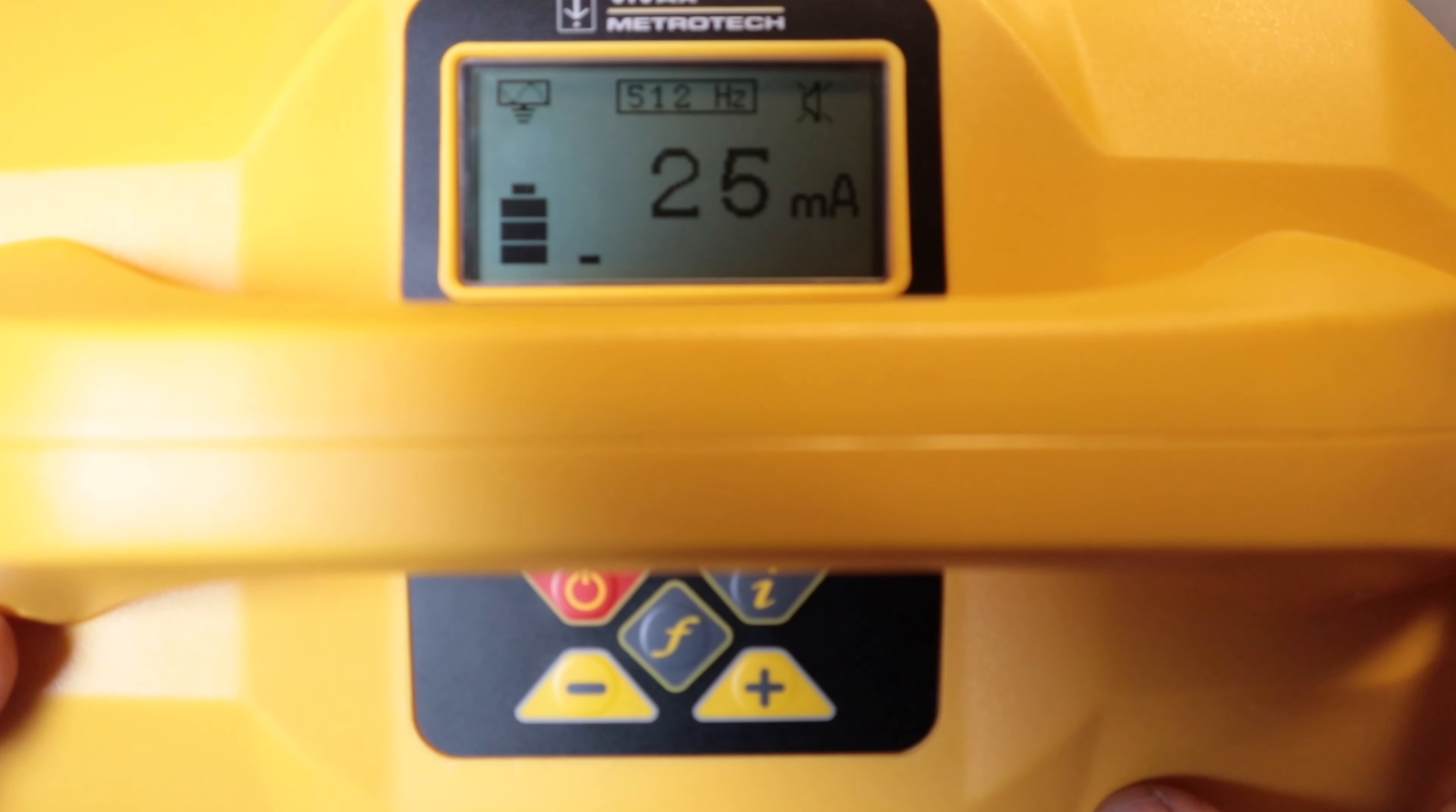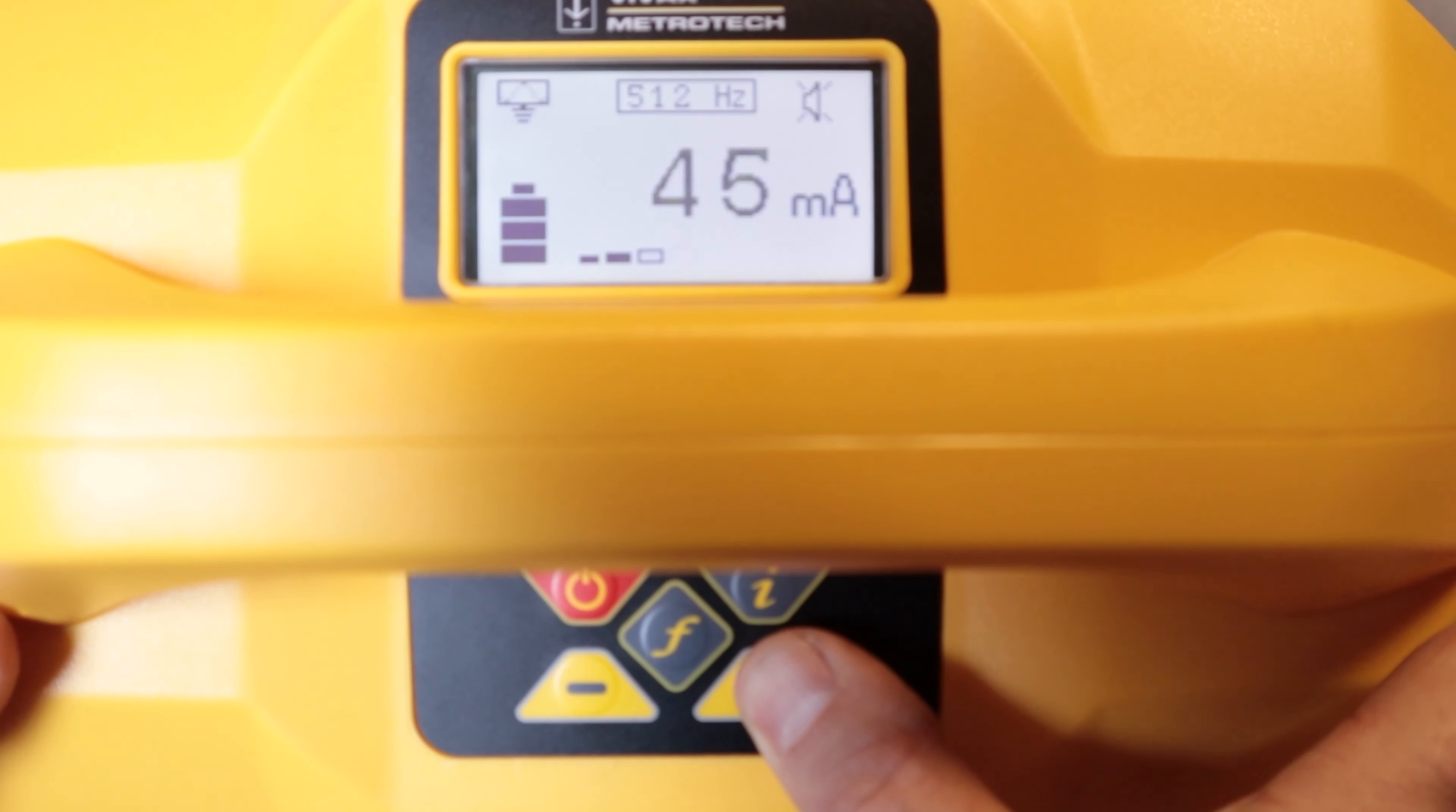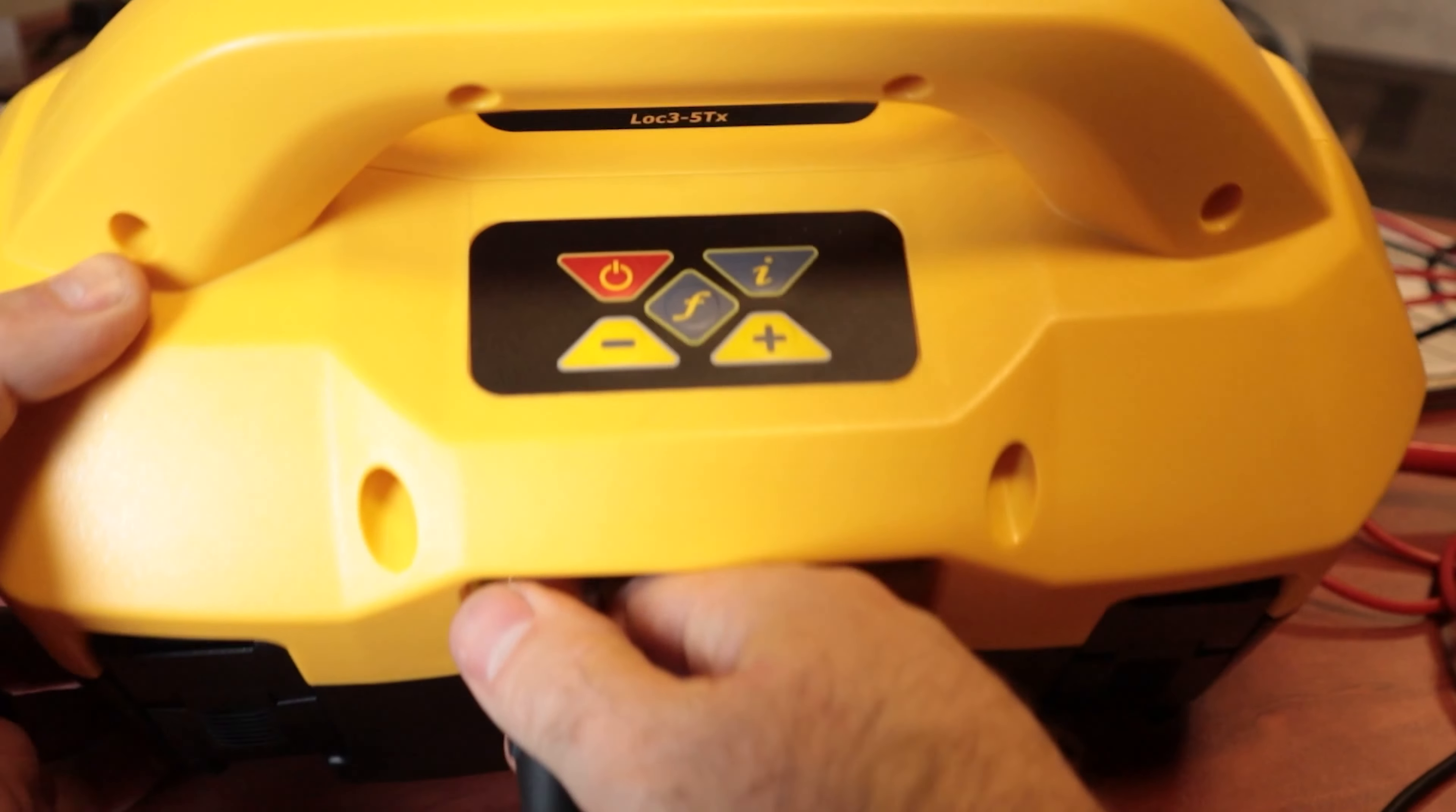Now I have my leads plugged in which is shown by this indicator up here. It has changed me to 512 hertz because that's the last frequency that I was using when I had my leads plugged in and now I'm at 25 milliamps. These transmitters will try and self-regulate to 25 milliamps when they are just connected and on basic power level. I can increase the power output by pushing the plus button up and it will increase how much power I am sending out from this transmitter.